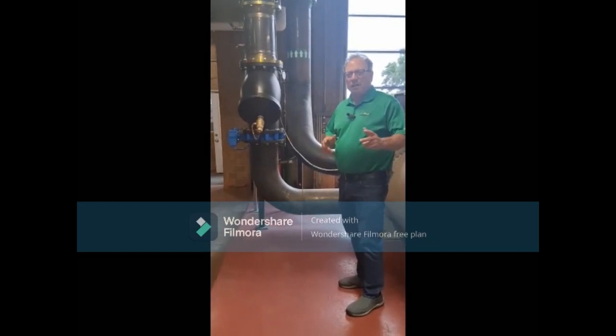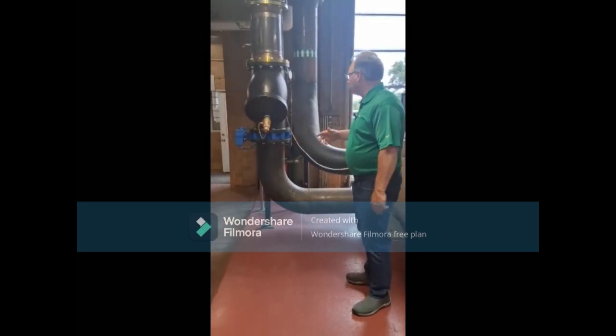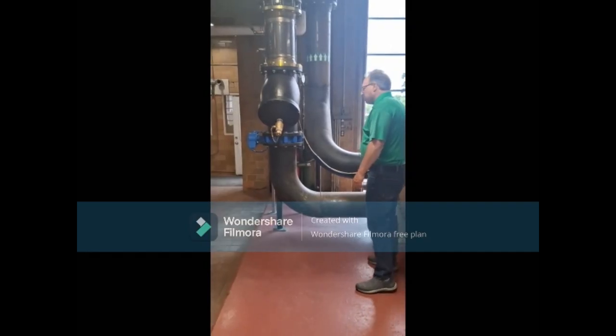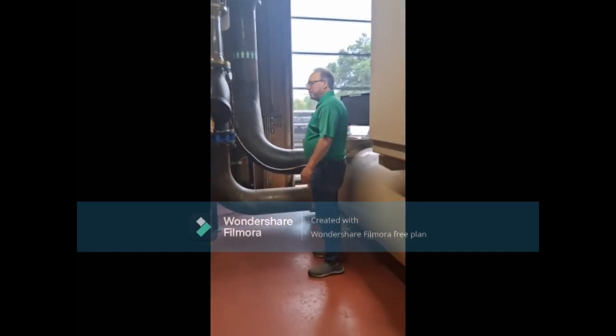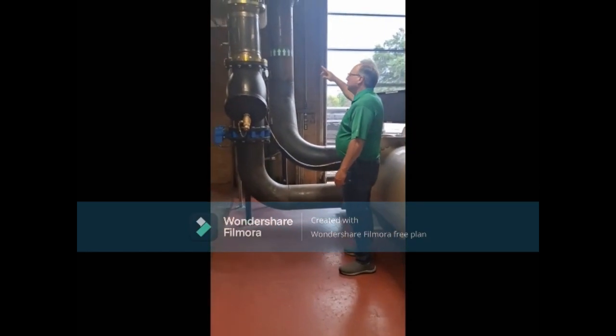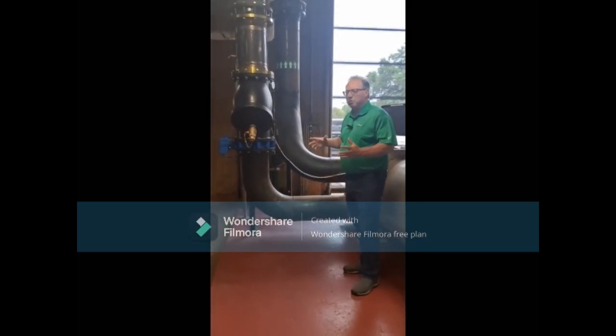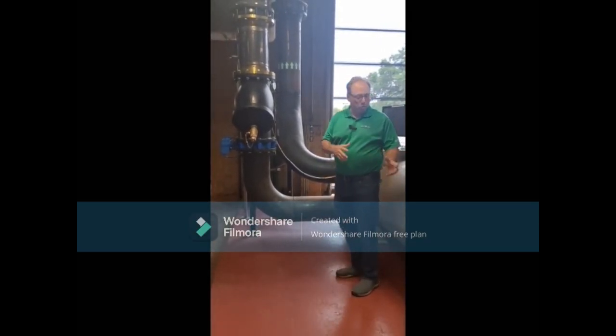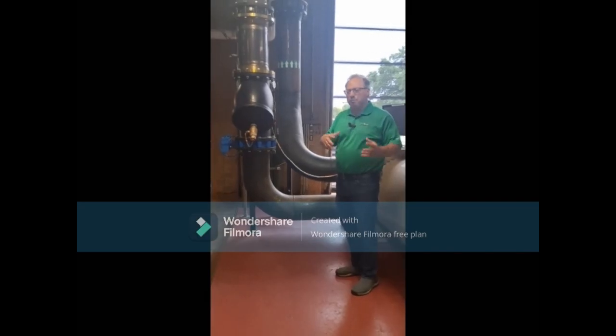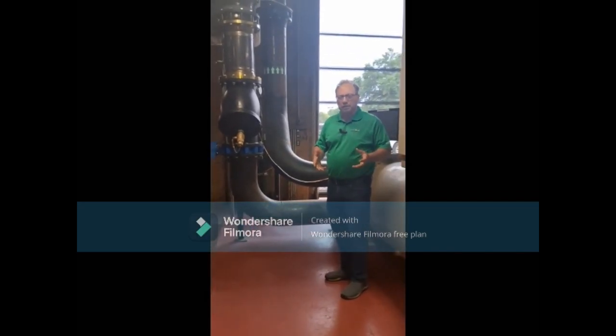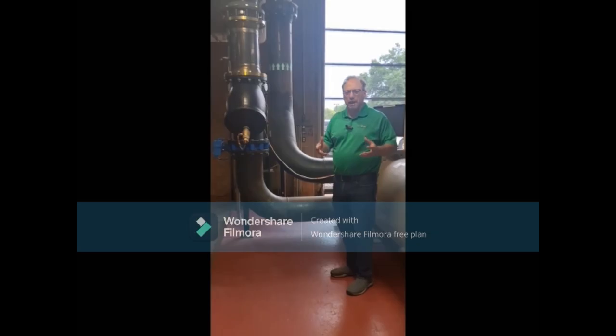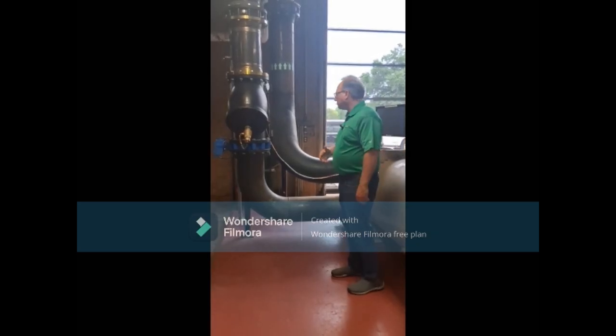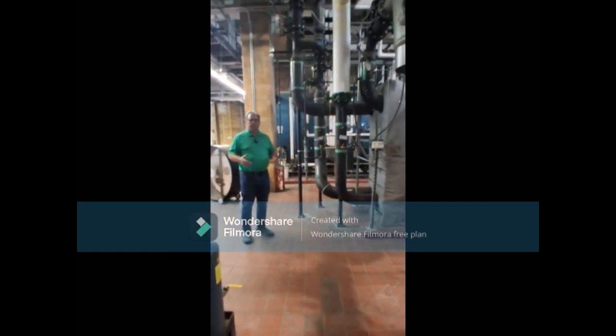Okay, this is the other side of the chiller, so you can see how we got the connection points on the body of the chiller, the piping, so we have continuity with all the piping as the same as the water inside, so we're positive in, positive out. It's a neutral environment. That's what keeps the scale and corrosion from happening in the chillers. Done. We're at the heat exchanger.